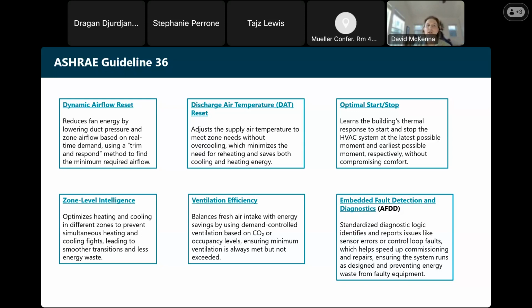A couple other examples here. Discharge air temperature reset is another good one. Historically, a lot of HVAC systems have provided just 55-degree air at a constant volume, and then you let the thermostat tell you to turn it off. What ASHRAE Guideline 36 is proposing is they really harp on the trim and respond logic. So we actually do the opposite. Now what we're doing is setting that discharge air temperature as high as we possibly can to save energy, until one of those zones basically cries uncle and says, oh, it's too hot, so we actually need to reset it further down. And so again, these are, on the software side, some of the strategies that we can look at to incorporate into our mechanical design to try to take advantage of some of these energy savings and optimization.